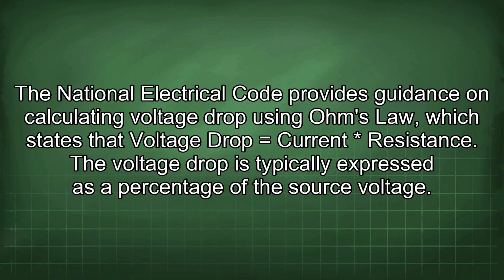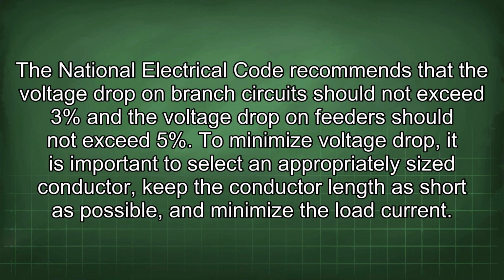The National Electrical Code provides guidance on calculating voltage drop using Ohm's law, which states that voltage drop equals current * resistance. The voltage drop is typically expressed as a percentage of the source voltage. The National Electrical Code recommends that the voltage drop on branch circuits should not exceed 3% and the voltage drop on feeders should not exceed 5%. To minimize voltage drop, it is important to select an appropriately sized conductor, keep the conductor length as short as possible, and minimize the load current.